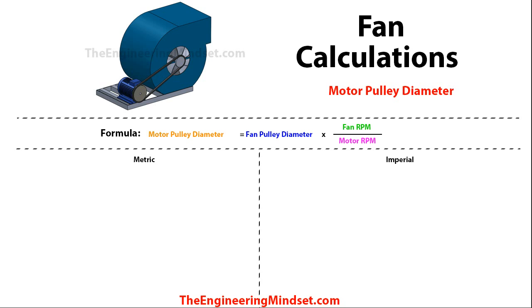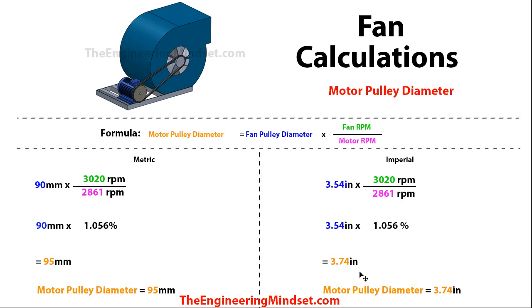So the next thing we can calculate is the motor pulley diameter. There could be various reasons why this has changed — say there's a new motor being replaced or a new fan has come in — and you want to know what diameter that pulley needs to be to achieve the correct airflow rate. The formula is: the motor pulley diameter is equal to the fan pulley diameter multiplied by the fan revolutions per minute divided by the motor revolutions per minute. If we drop the numbers in — the fan has a 90 millimeter diameter pulley, or 3.54 inches — doing the division between the two RPMs leaves us with a ratio of 1.056. Multiplying that by the fan pulley diameter gives us 95 millimeters, or 3.74 inches, for the motor pulley diameter.